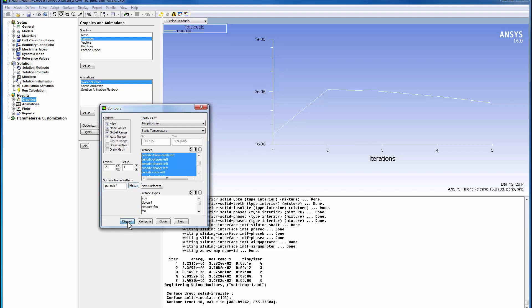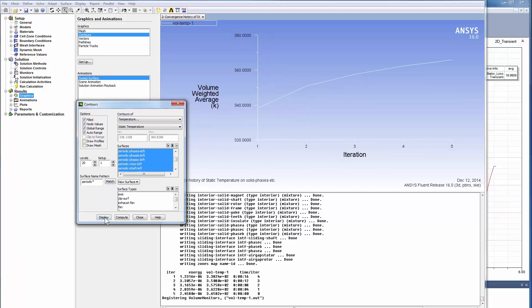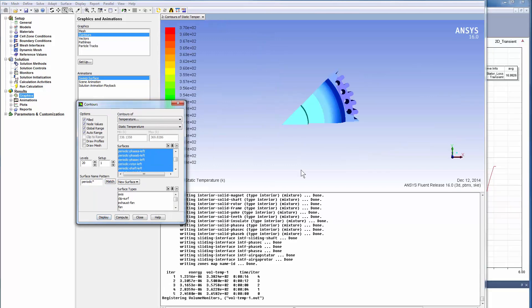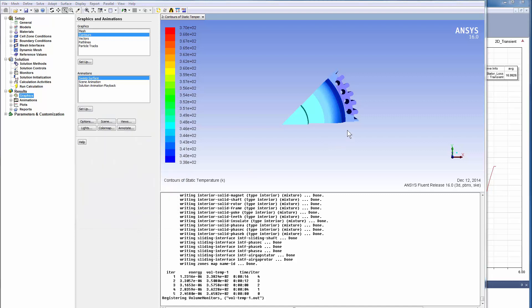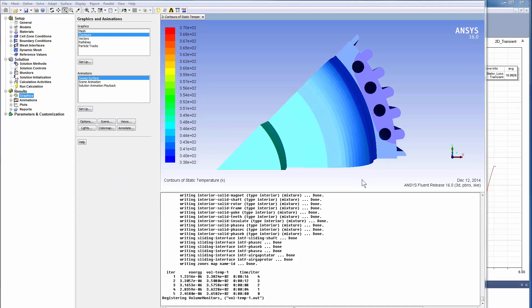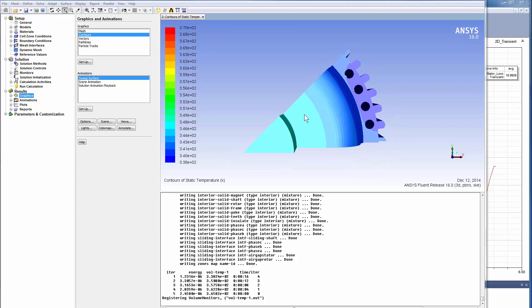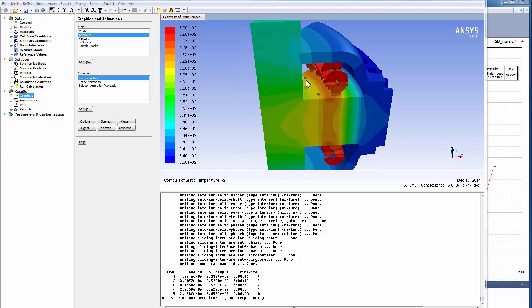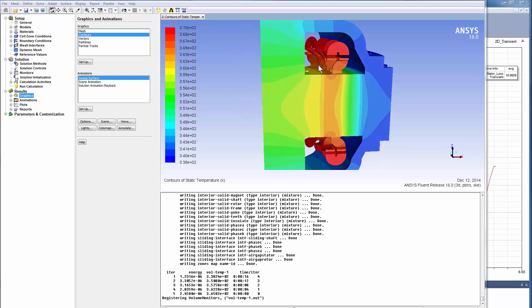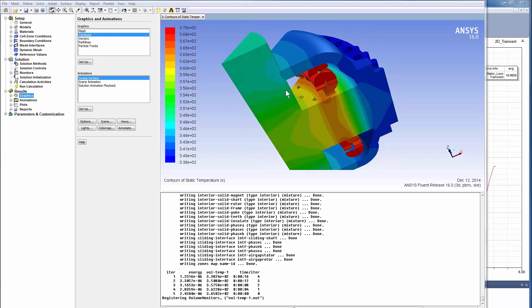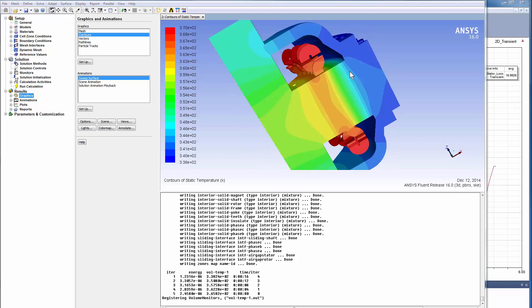Finally, we see the temperature profile. Here the temperature distribution for a given electromagnetic input across different objects is shown. Temperature is higher at the end winding and within the core, the temperature is lower.